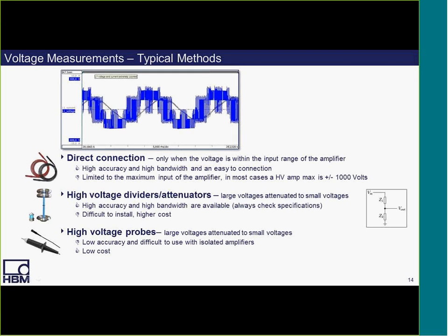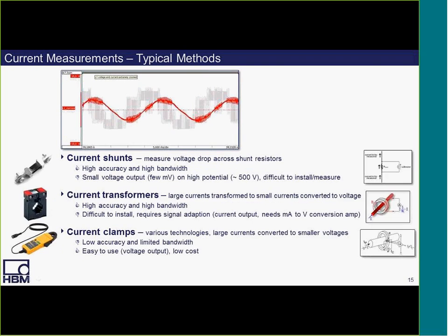So another alternative for voltages higher than 1,000 volts would be a high voltage divider or an attenuator. It's going to take the large voltages and attenuate them to a smaller voltage. The plus there is you have high accuracy and high bandwidth voltage dividers available. You want to make sure you do check the specifications. However, it may be difficult to install, and they do come at a higher cost. High voltage probes pretty much do the same thing. Basically, a large voltage is attenuated to a smaller voltage. However, they have low accuracy and are difficult to use with isolated amplifiers. The only positive there is they do come at a low cost.